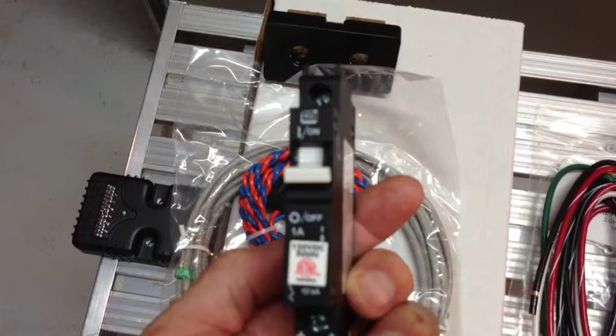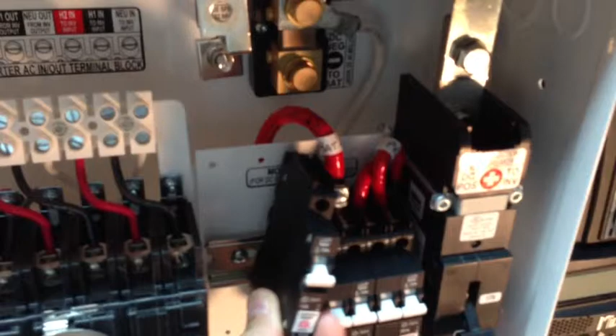So I've chosen to put 1 amp DC circuit breakers in and wire them into the panel. It'll go in this slot right here, and by the time I get that one installed plus one more, that'll leave me two additional slots for anything else that comes up that needs to be wired in.